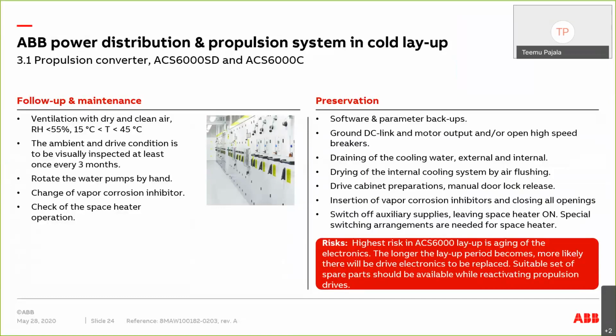And those are extremely important if the vessel is in the cold environment, so that there is no ice coming in the system. Maybe not that relevant for the operational vessels or vessels that have been in operation, but this has been very important for the new build periods when the equipment has been at the yard to avoid any ice in the water system and ice breaking the pipes and seals. And space heaters, they need to be on. Otherwise, power supply is not needed. So all the power can be switched off from the drives, and only space heaters left on. And even for cooling fans or cooling pumps, there is no need to have power available. Those can be rotated by hand, just to have some movement for them, so that they don't get stuck.